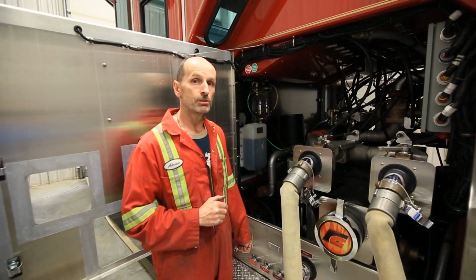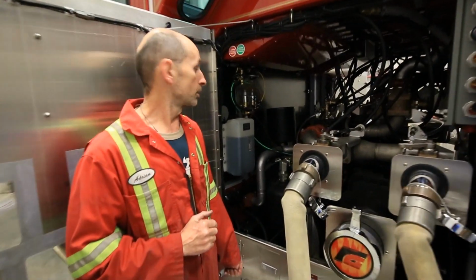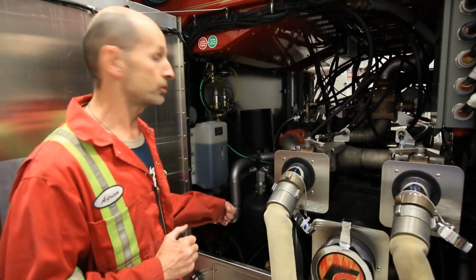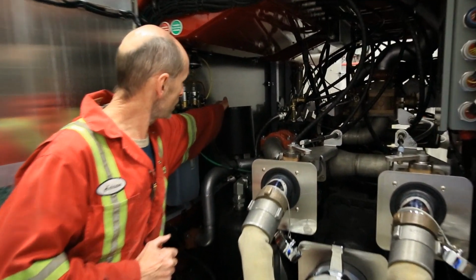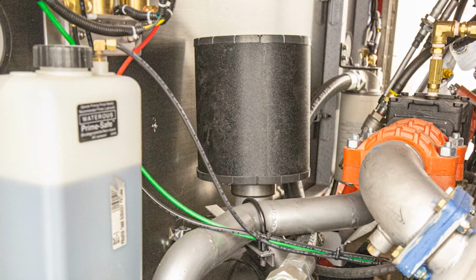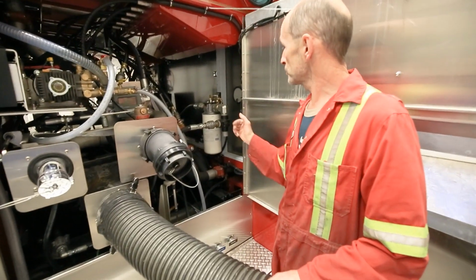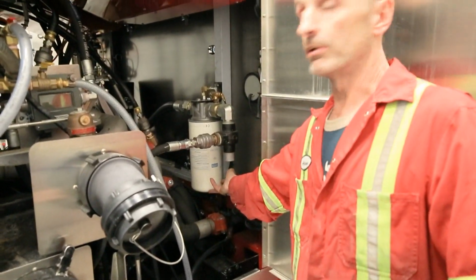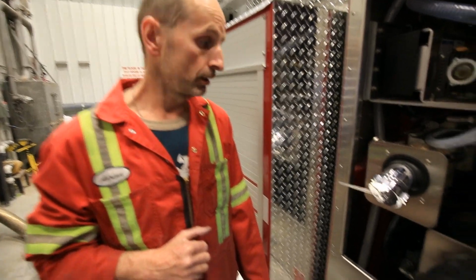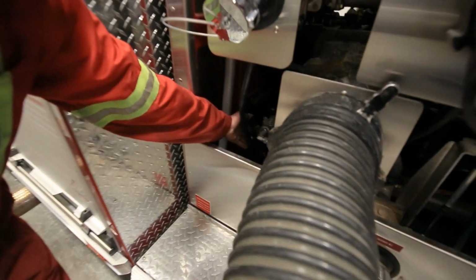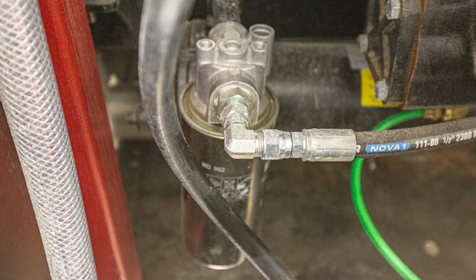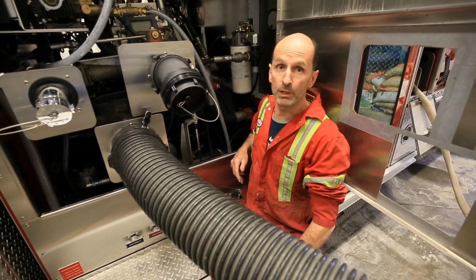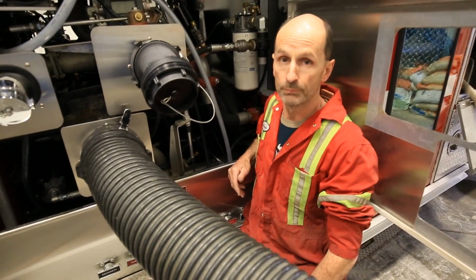There are 3 filters on the system to be checked according to the manufacturer's schedule. First of all, on the intake of the compressor, just behind the main inspection door, there is an air filter. On the curb side, inside the inspection door, there is an oil air filter. Also on the curb side, below the pump intake, there is the oil filter for the system, which is attached to the heat exchanger.